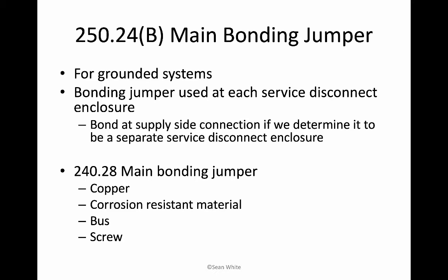705.11. That's 2020 NEC, or we'll call it 705.12(A) in the 2017 and earlier versions of the NEC, but they're pretty much the same. And our main bonding jumper, what can it be? According to 250.28, it can be copper, so it can be like a wire. It can be a corrosion-resistant material. It can be a bus bar, and it can even be a screw. So if you look in your main service panel, a lot of times it's a bus bar, and you just see this one bus bar that has bare copper going to it, green wires going to it, and white wires going to it. And that would be where everything is connected together.